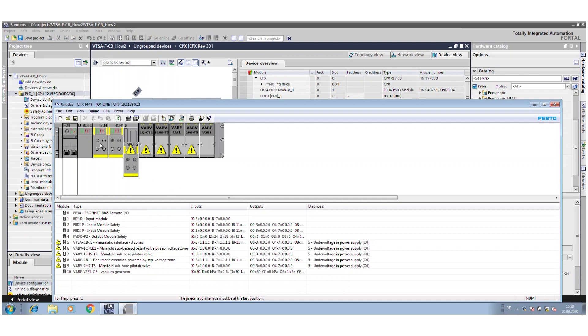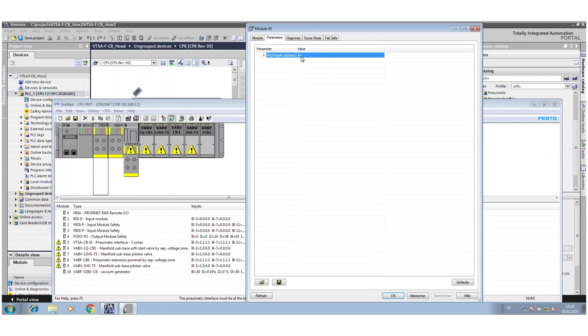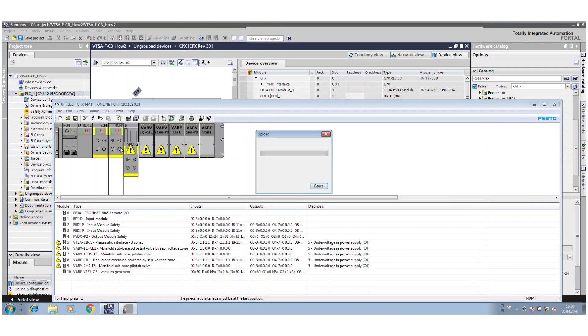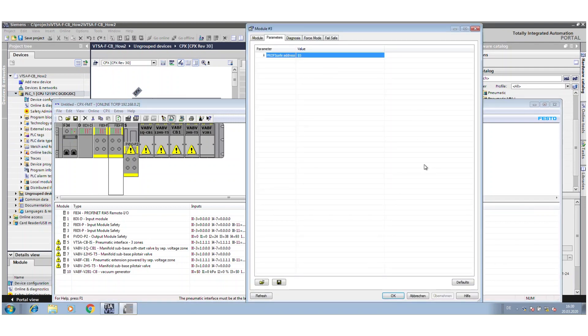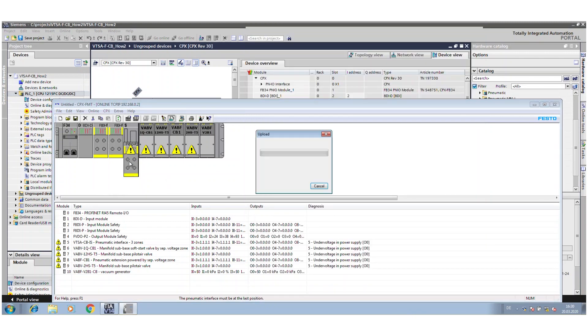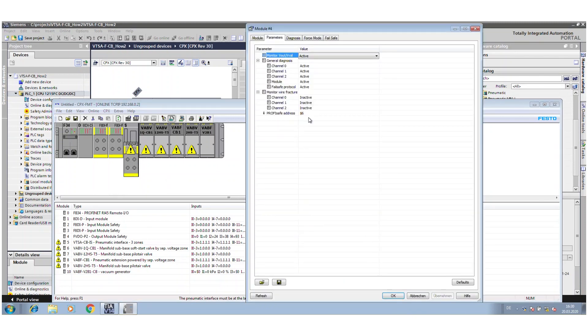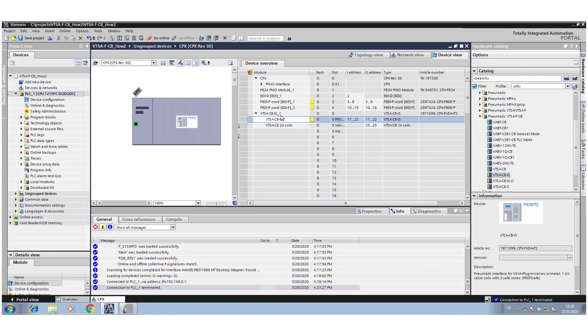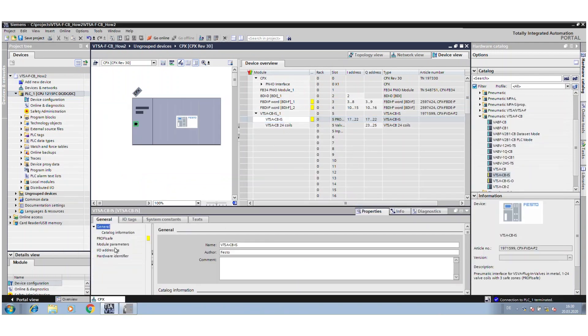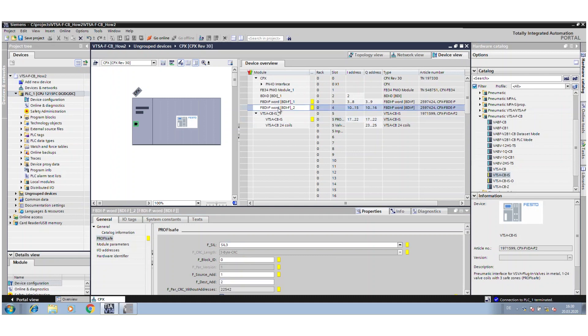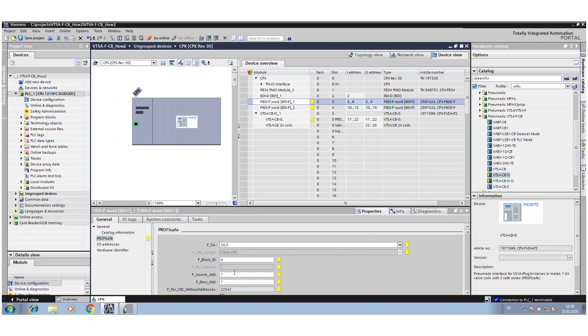When you pull it into the configuration, it's marked yellow, and so there is the safety configuration to do. We also check the safety addresses. Sometimes people forget it. Here it's 4 for the safety module, 5 and 6 for the interface.